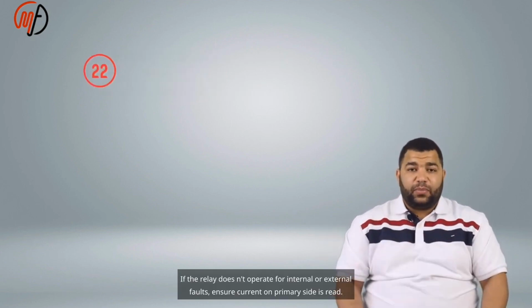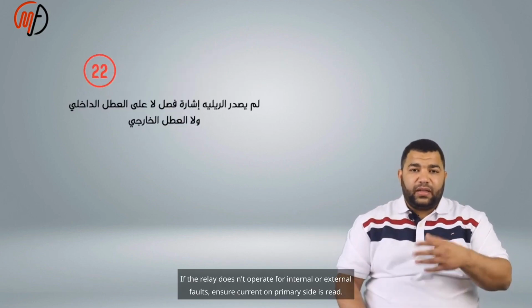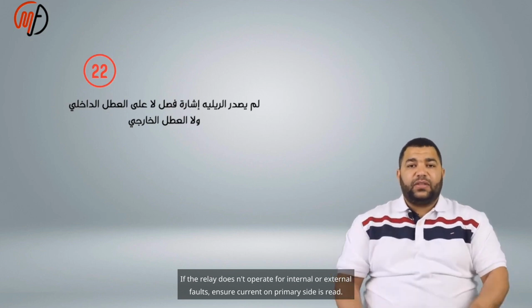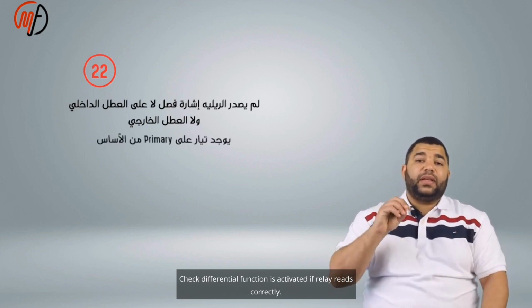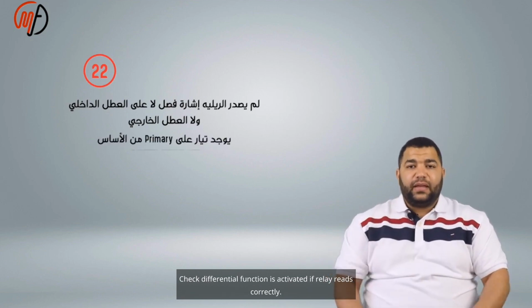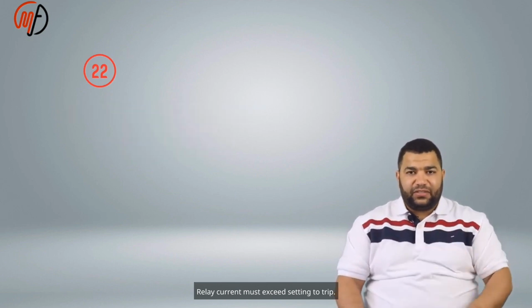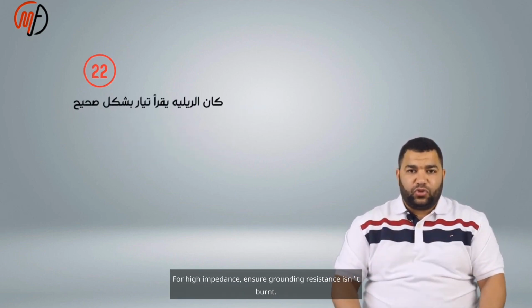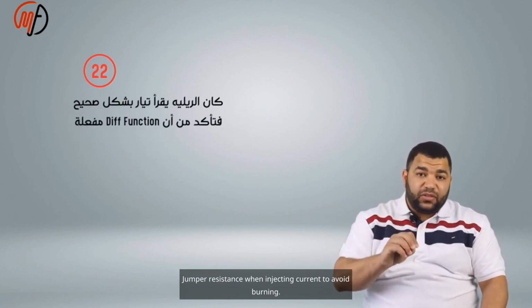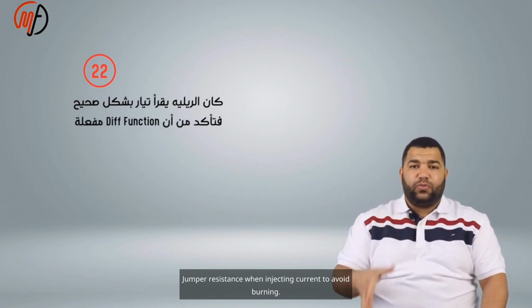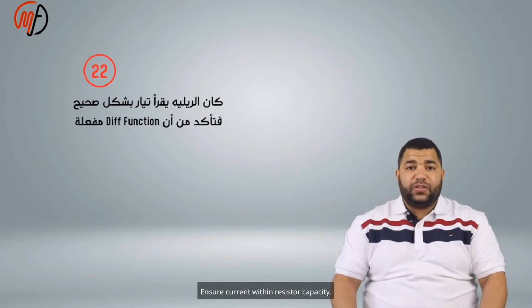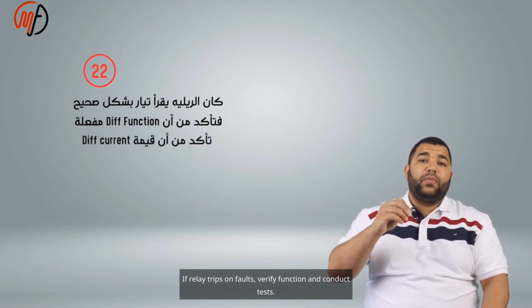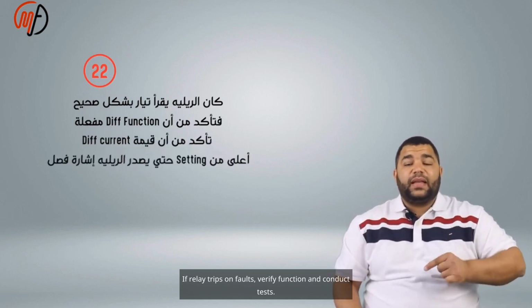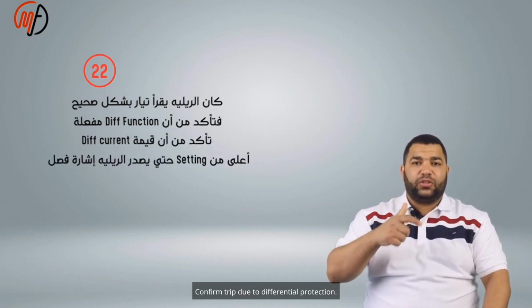If the relay doesn't operate for internal or external faults, ensure there is current on the primary side. Check that the differential function is activated if the relay reads correctly. Relay current must exceed the setting to trip. For high impedance, ensure the grounding resistance isn't burnt. Jumper the resistance when injecting current to avoid burning. Ensure current is within resistor capacity. If the relay trips on faults, verify the function and conduct tests. Confirm the trip is due to differential protection.